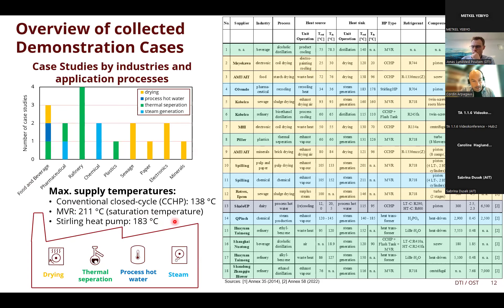What we can see is that conventional closed heat pump cycles reached temperatures up to 138 degrees using HFO refrigerants in this case. But MVR goes higher, to 211 degrees saturation temperature, with piston compressors and multiple cylinders. Then we have Stirling heat pumps that also reached higher temperatures, up to 183 degrees.